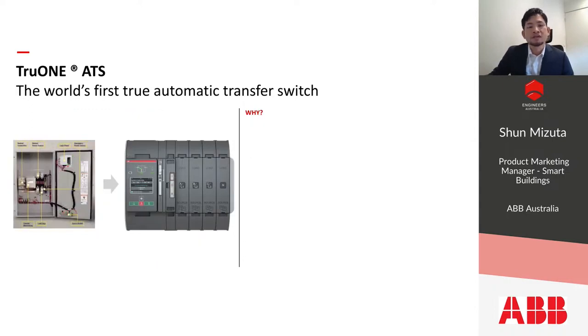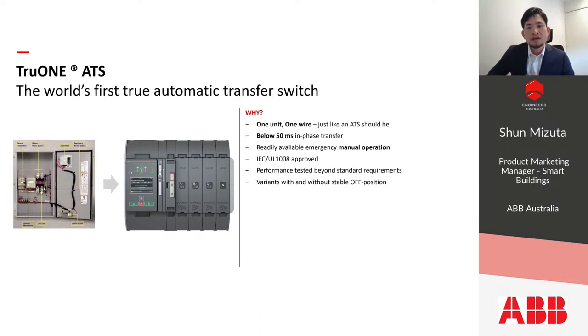If you look at the picture on the left, that's the conventional type of ATS. You see many components wired together, a very complex design. Now, True One has put everything into one device. It also has an in-phase transfer time below 50 milliseconds, which is one of the quickest in the market. And it has manual operation ready to be used in case of emergency. You don't need to disconnect source one, the primary source, or the secondary source to do that. Manual operation is ready when the power is on.